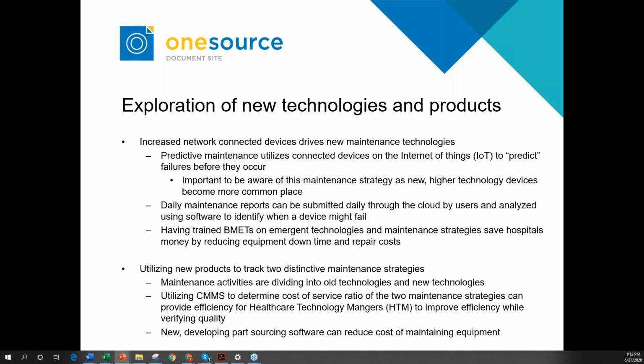It's important to be aware of this maintenance strategy because these devices are becoming more commonplace. And like I said, daily maintenance reports can be submitted through a cloud system by the users, and they can be analyzed using special diagnostic software by the biomeds, so they can identify when it might fail rather than after it fails, or just following a standard preventative maintenance procedure.